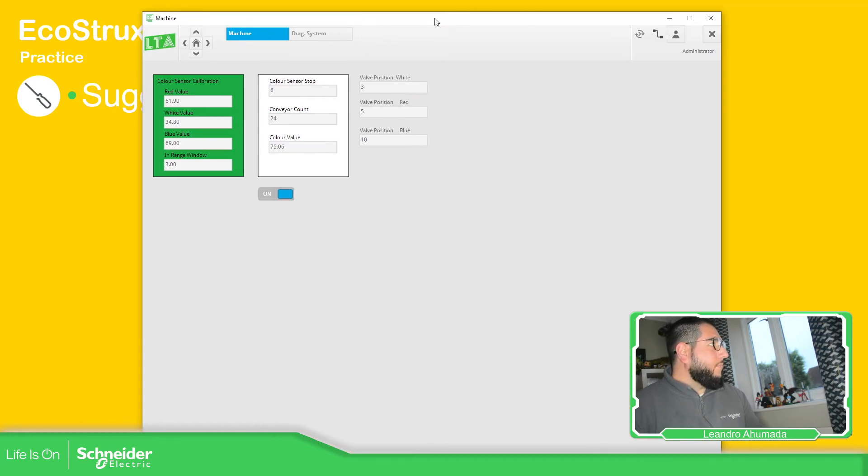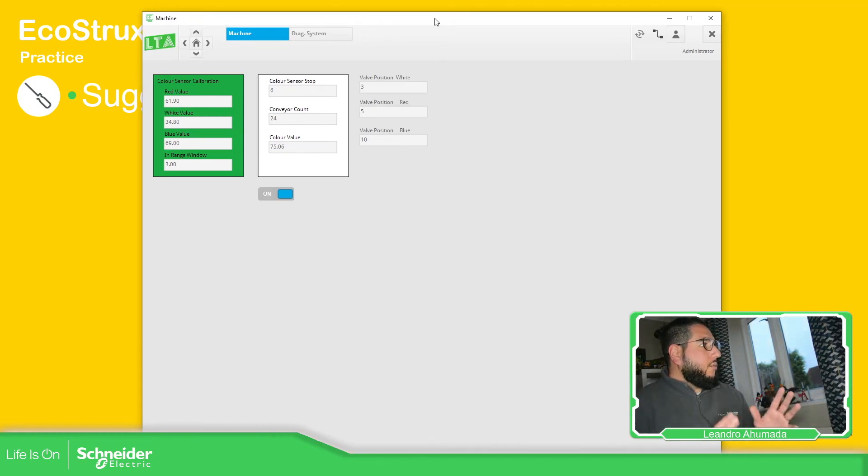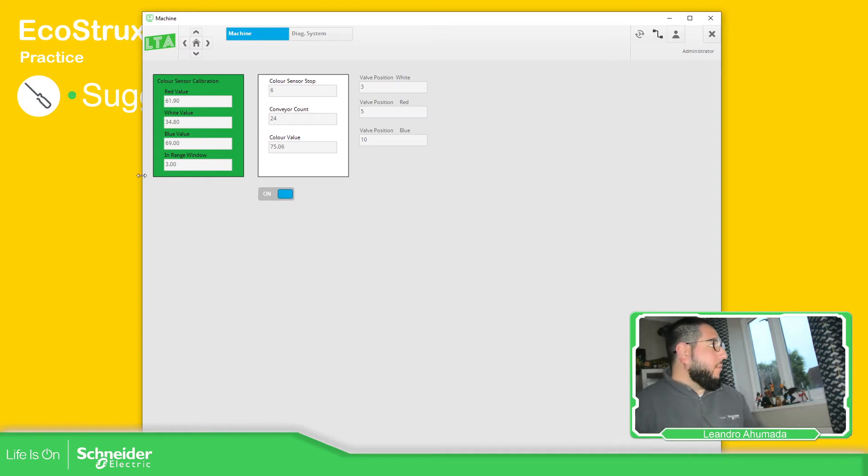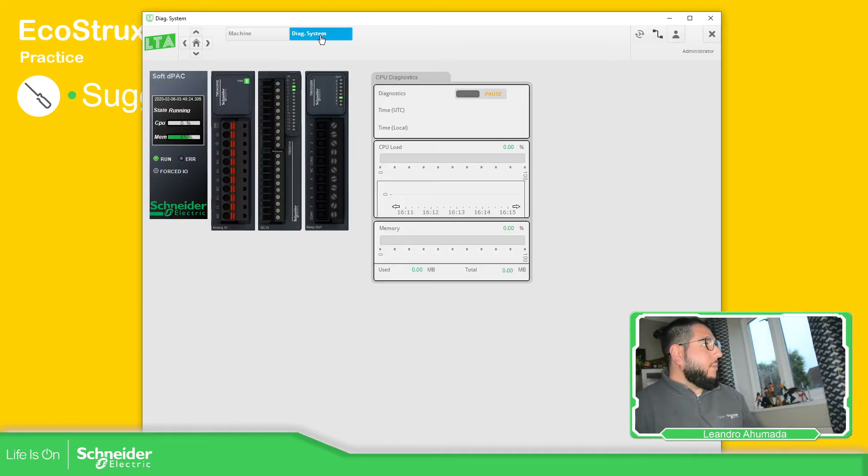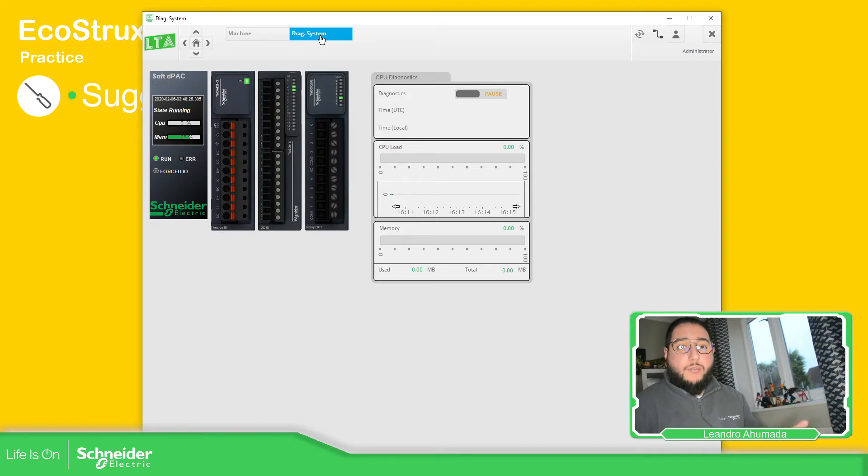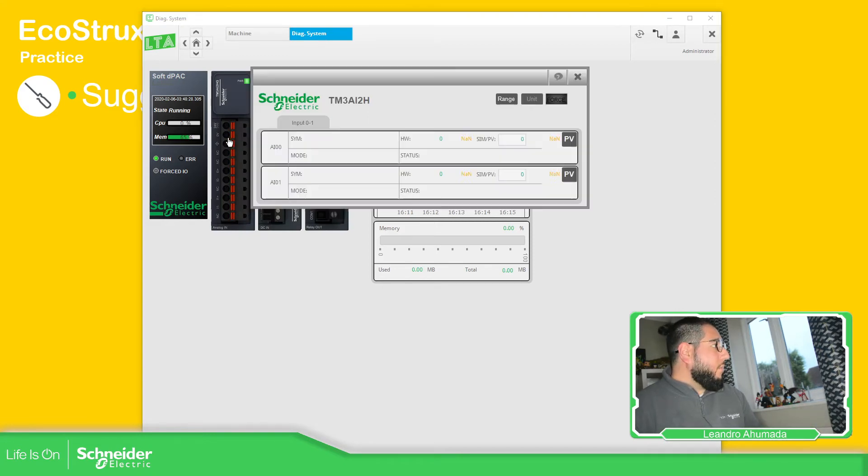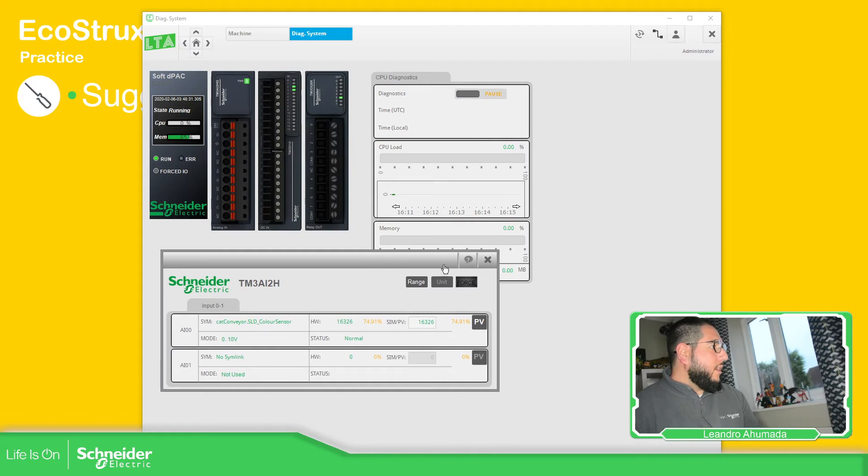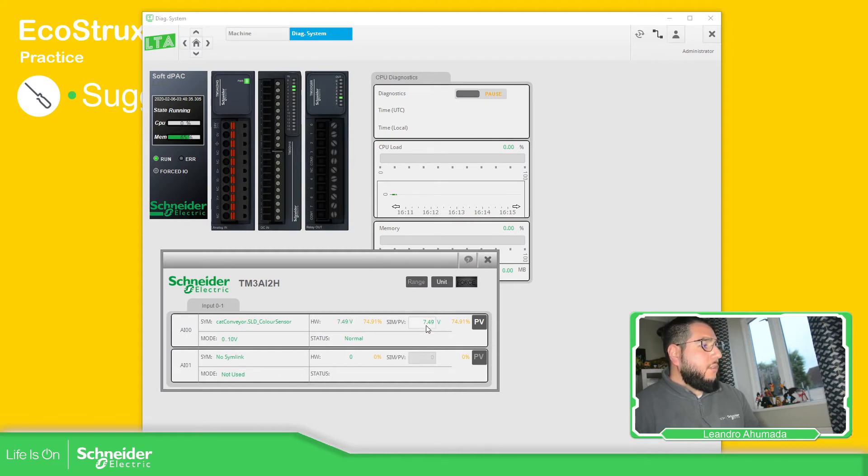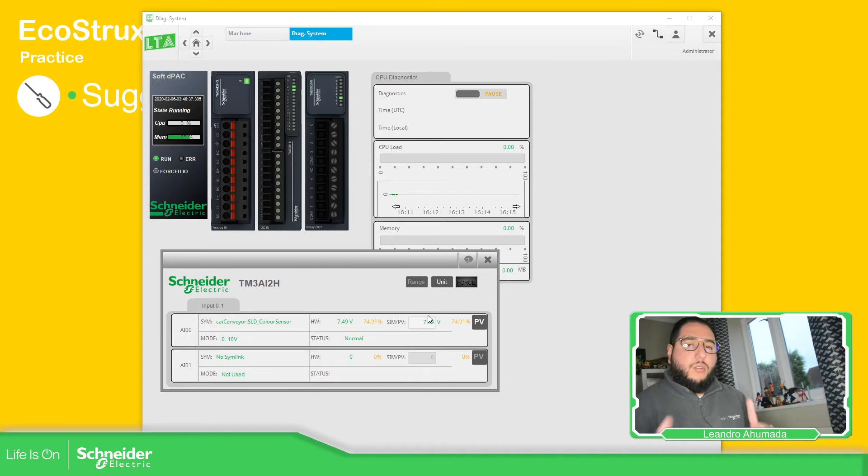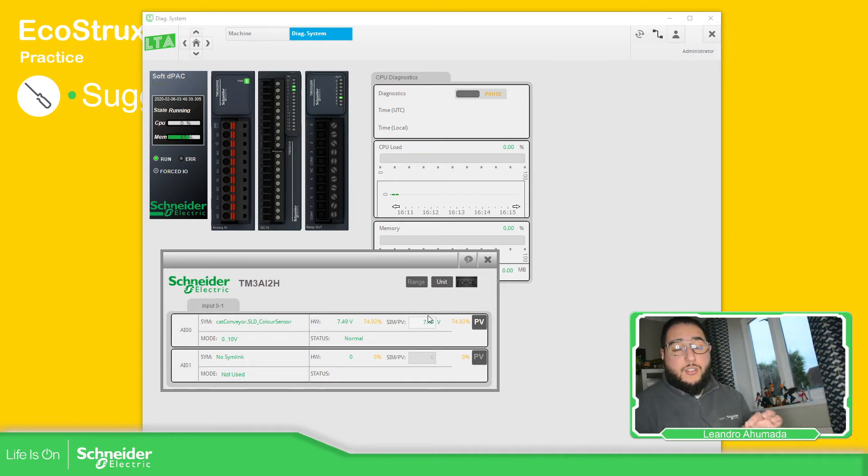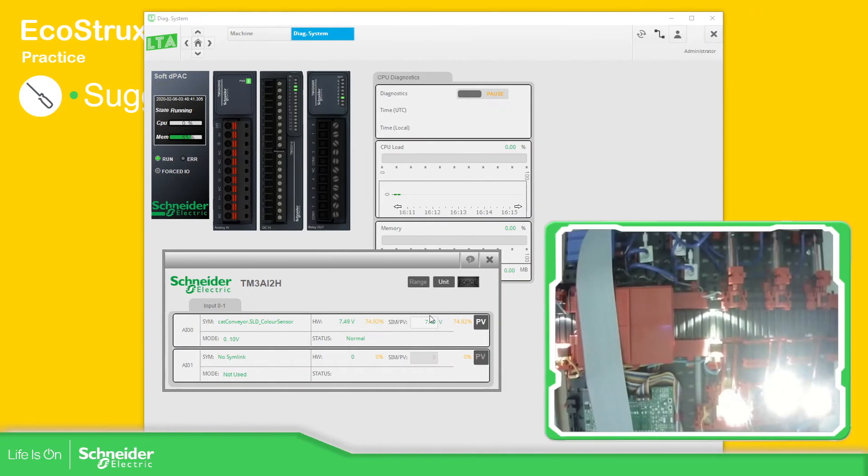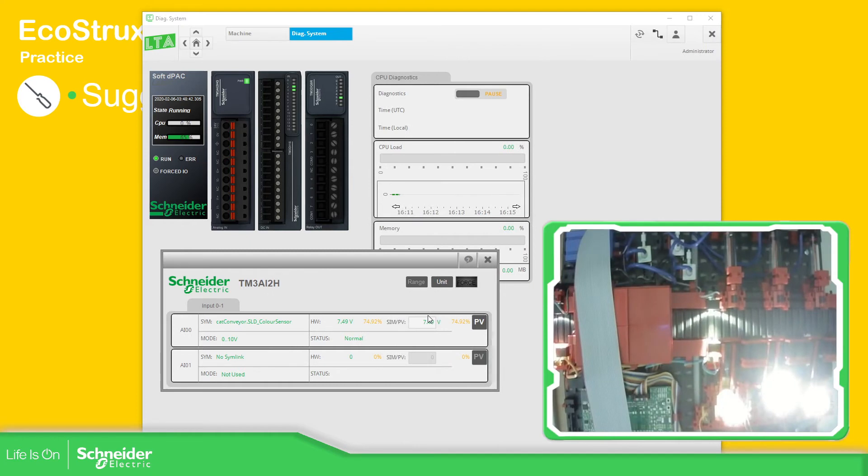In order to calculate the sensor calibration, I recommend you go to the system we've already defined and open the analog input part. In the analog input, you have this unit. This is the value we can use to validate the sensor. Let's take a look. Here you can see 7.49 - this is the value when there is no object in there.